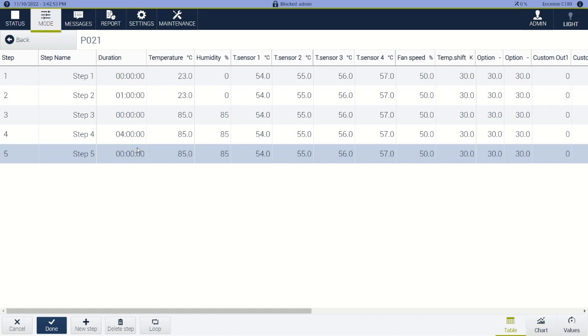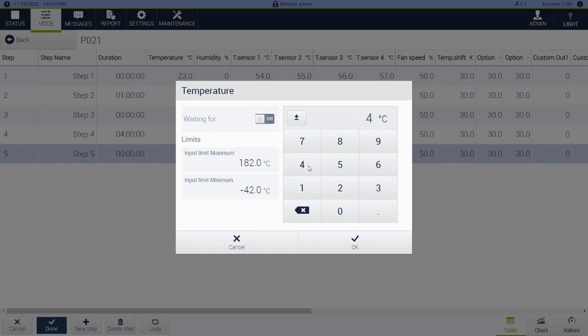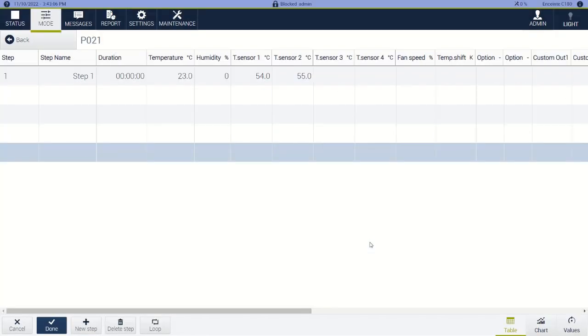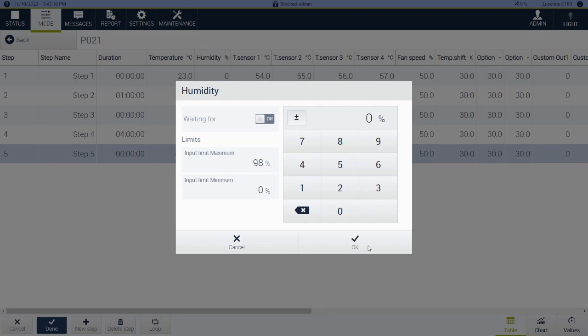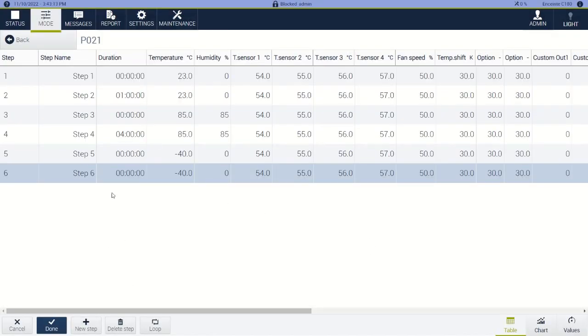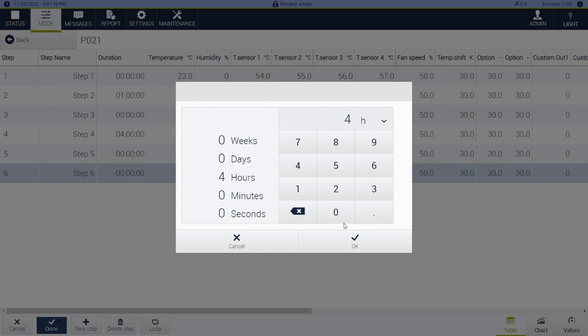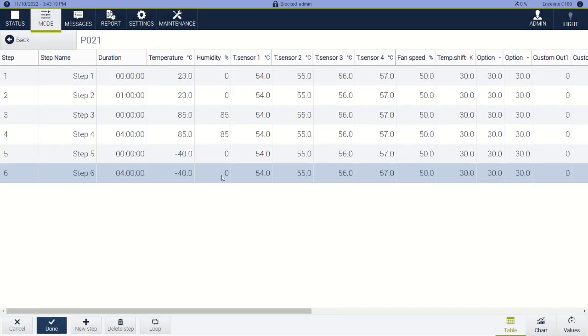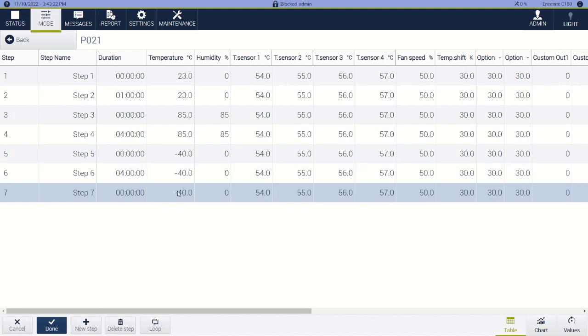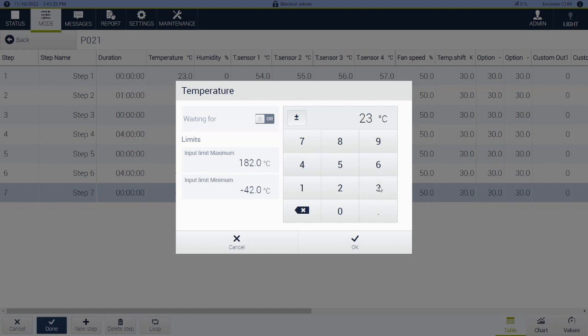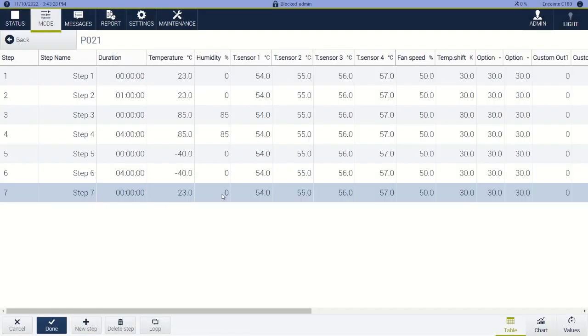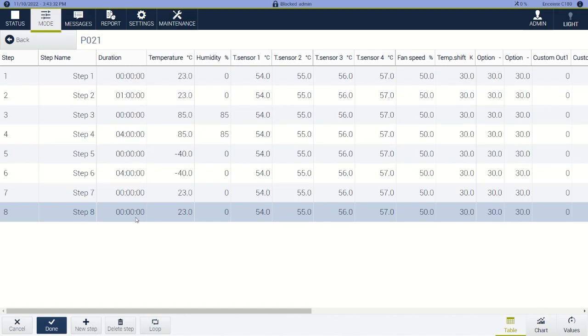Now I want to jump back down. Let's make it more interesting — let's say I want to go to negative 40°C, so I will do 40 negative, and 0% humidity. Let's say I want to stay there for four hours. And then after all that's done, I want to go to ambient again — so 23°C and 0% — and I want to stay there for four hours to make sure everything is conditioned back to ambient.